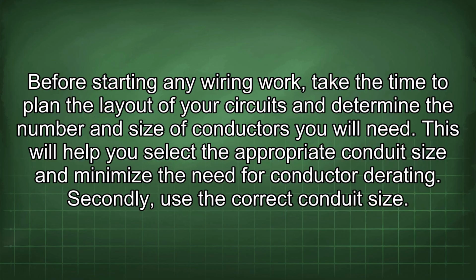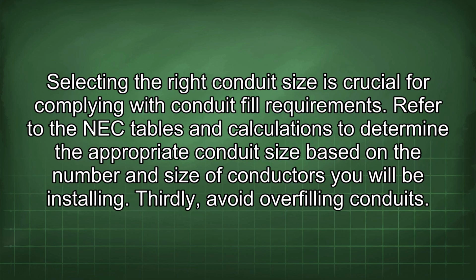Secondly, use the correct conduit size. Selecting the right conduit size is crucial for complying with conduit fill requirements. Refer to the NEC tables and calculations to determine the appropriate conduit size based on the number and size of conductors you will be installing.